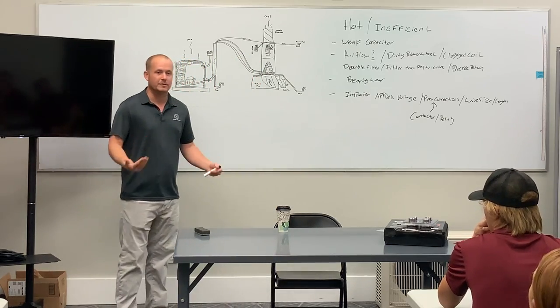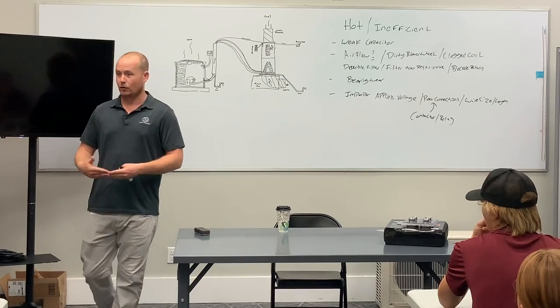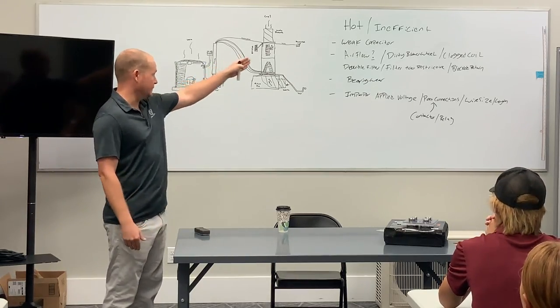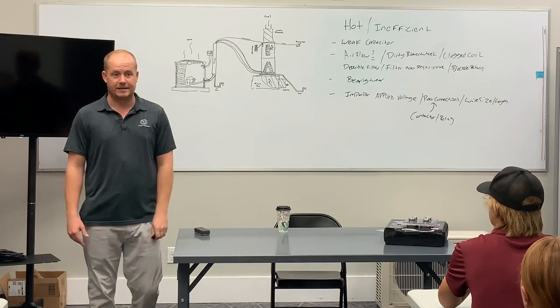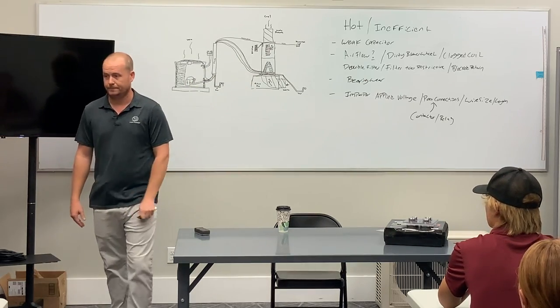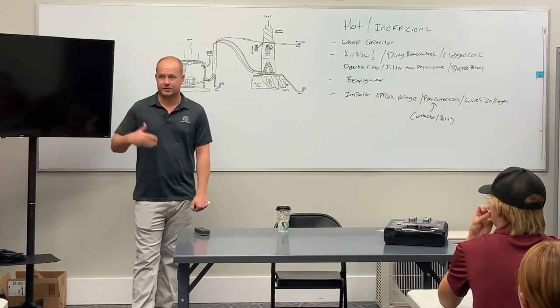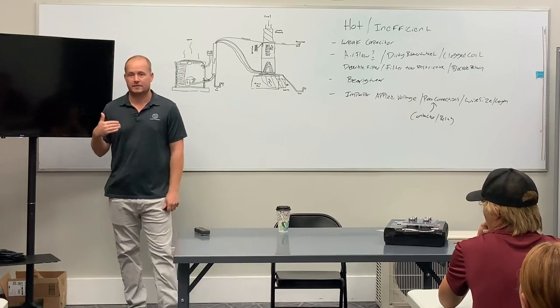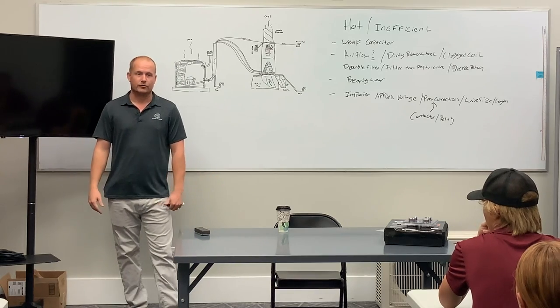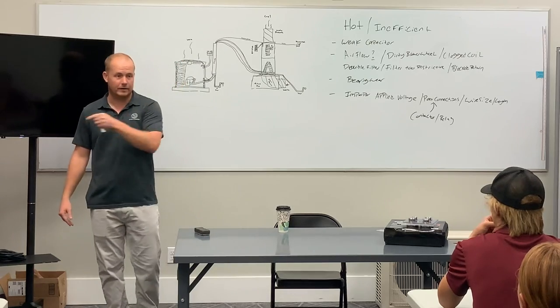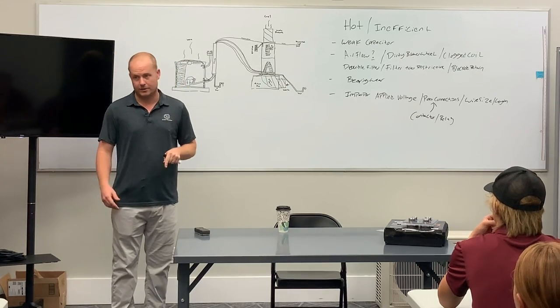But what we do is, when it does need one of these things, for a reason, the reason why we're presenting it to the customer is because it prevents heat and inefficiency in a motor, and that is all true, right? You don't just replace a capacitor when it's 10% low or suggest replacement because that's just company policy. You do it because a capacitor that's 10% or more low results in hot and inefficient motor operation.